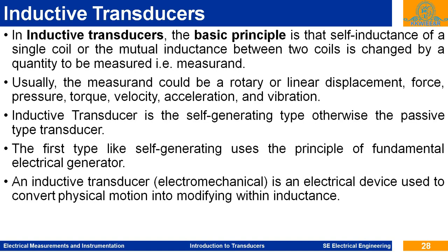So it will give a 75 volt DC output for 1500 rpm, and we set this 75 volt in the closed loop system as a set point. As there is a change in the process, there is a change in the speed, so it will give the variable voltage, based on or proportional to the speed.